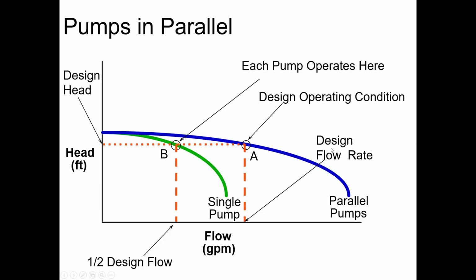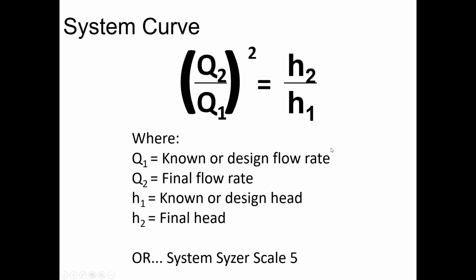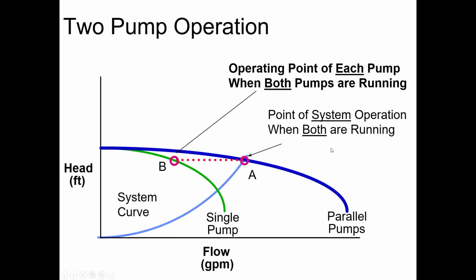Now the pipe sizing is sized to the total flow, right? You've got to start with that. You have to understand that I'm not sizing it for one pump. I'm sizing it for 2 pumps working together to that desired flow rate. So again, there's that system curve formula, or just use scale 5. And what we want to make sure, and again, software today does it for us automatically, whenever you guys get involved with selecting parallel pumps, they're going to build a system curve. And what we want to know is, okay, each pump operates at B, double it. Here's my combined operating point.